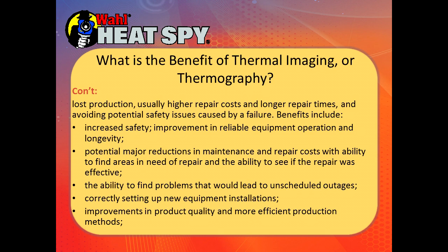We have the ability to find problems that would create unscheduled outages and to correctly set up new equipment installations. If you're buying a new piece of machinery and want to develop a maintenance history, when you first turn it on take some thermal images to get a baseline, then monitor it monthly, every six weeks, or every three months — whatever schedule you set up — and see what's changing. That way you can determine when a problem may be approaching. You can also improve methods and quality of efficient production.